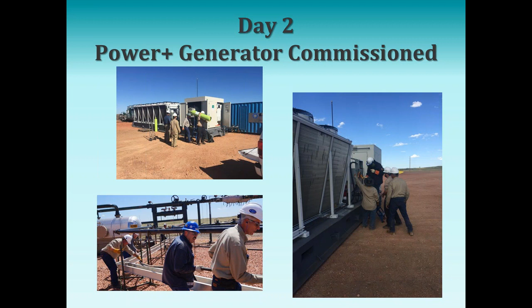So the question was, would we use glycol? In the boiler, yes, if this unit stays here, we'll put 50% glycol in it. Talking with the boiler company out of Fargo, North Dakota, who's been servicing this boiler for us, along with a heater that runs off gas with a thermostat, when it gets down to 20 and 30 below, that heater comes on to preheat the air that is used by the boiler. It can be winterized, and there are boilers all over North Dakota that operate 12 months out of the year.